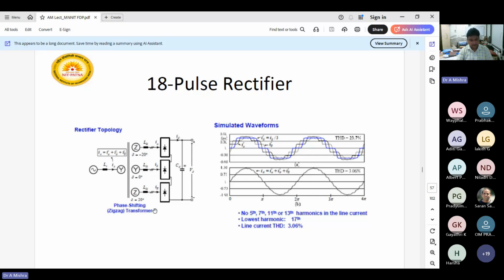Then coming to the 18 pulse converter, the first one is zigzag, the second one is star, the third one is again zigzag. So a zigzag transformer will be used. Total output will be 18 pulse, so the lowest harmonic present will be the 17th. Line current THD in the 12 pulse converter is 8%. Here in the 18 pulse converter it is 3.06%. So you are reducing the line current distortion.